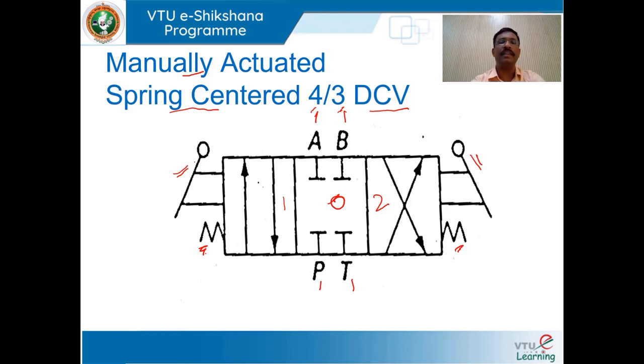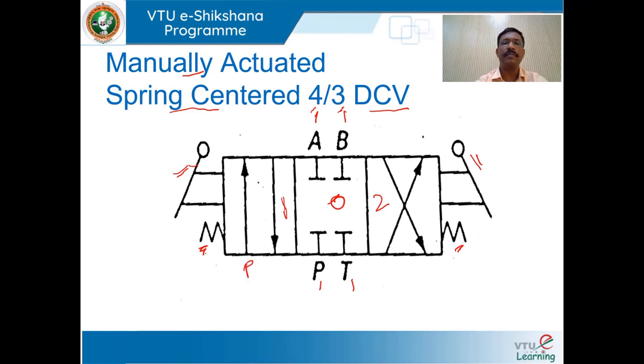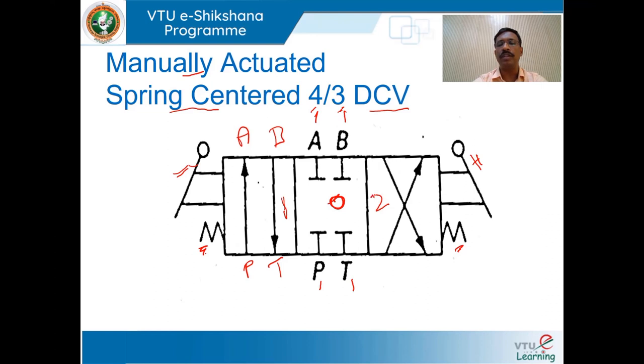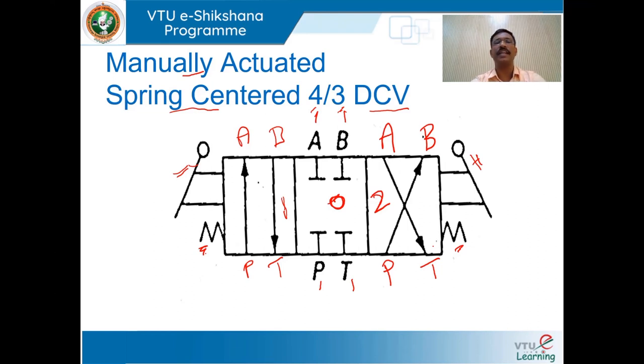When you operate the lever, the spool slides and shifts to position 1 — P connects to A and B connects to T. When you release the lever, opposing spring forces return the valve to position O. Operating the lever again shifts the valve to position 2 — this envelope configuration connects P with B and A with T. This is how to draw a symbol for a manually actuated spring-centered four-way three-position DCV.